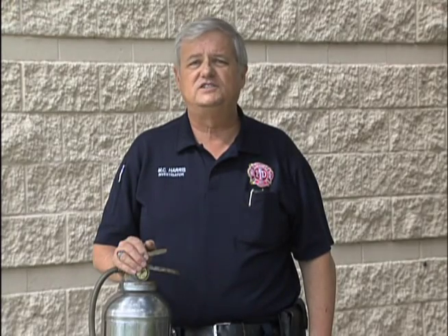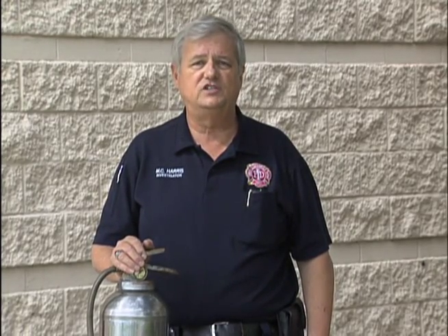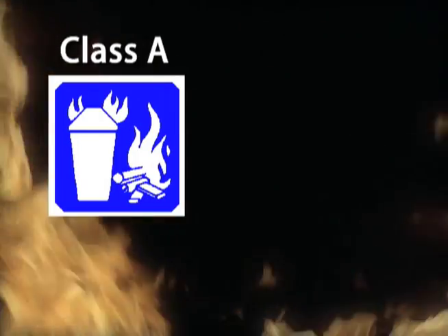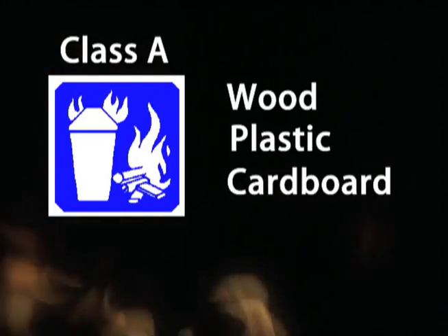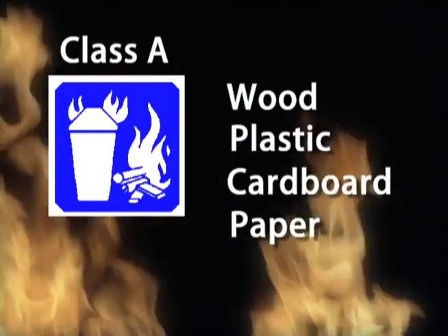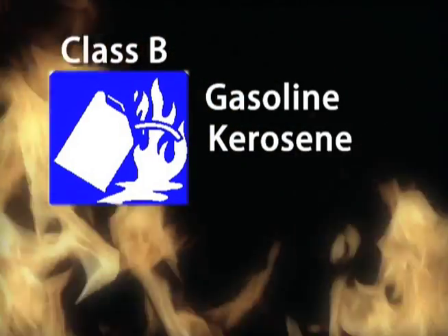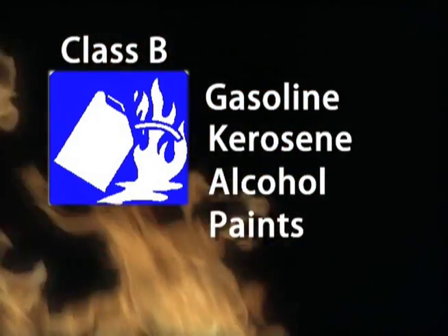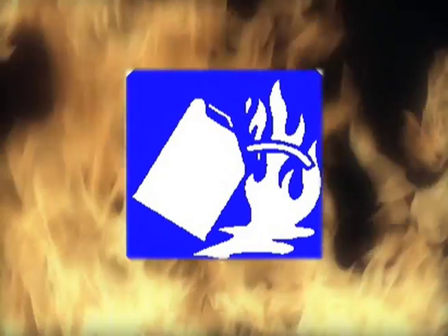There are 5 classes of fires according to what kind of material is actually involved in the fire. Class A materials involve ordinary solid combustible materials such as wood, plastics, cardboard, paper, things like this. The symbol for Class A on a fire extinguisher is a picture of a trash can with a fire around it. Class B involves flammable and combustible liquids such as gasoline, kerosene, alcohol, and some paints, varnishes, and thinners.